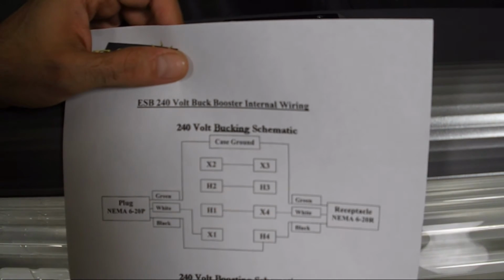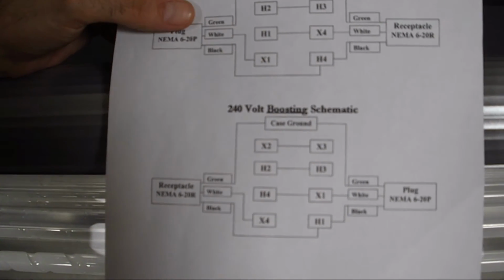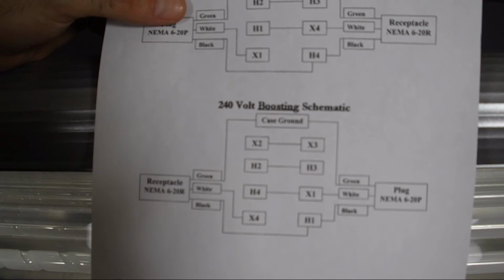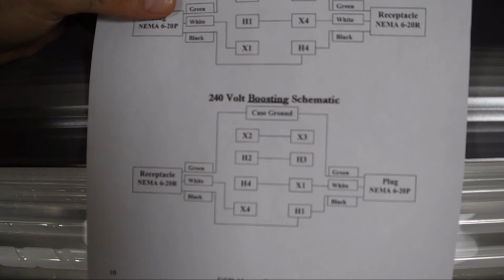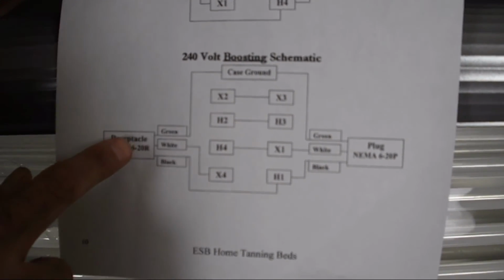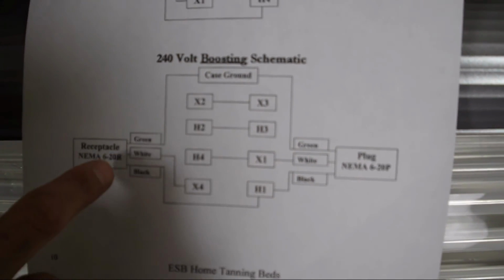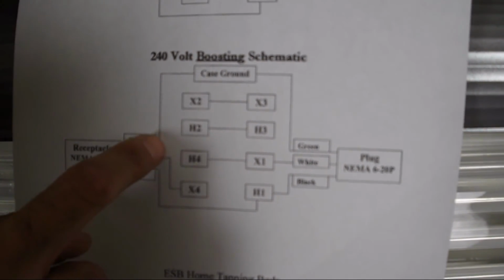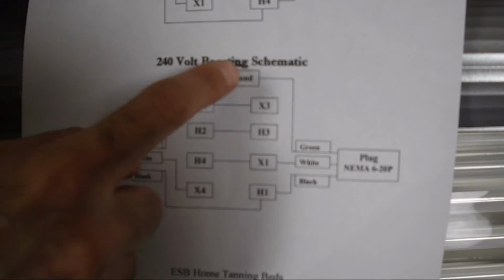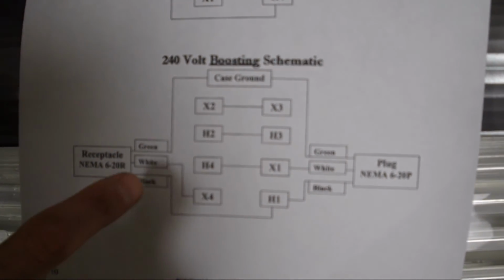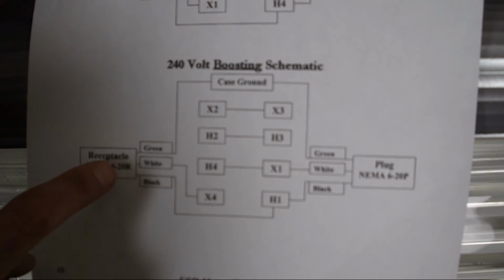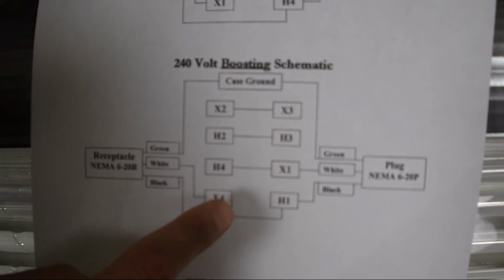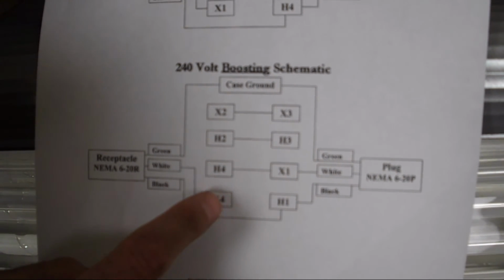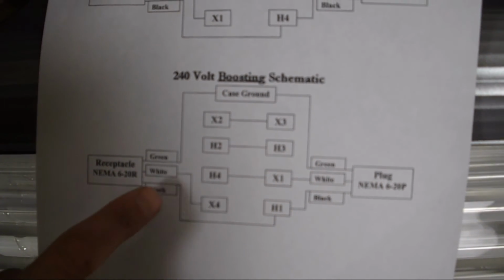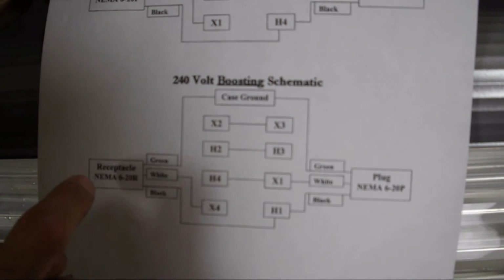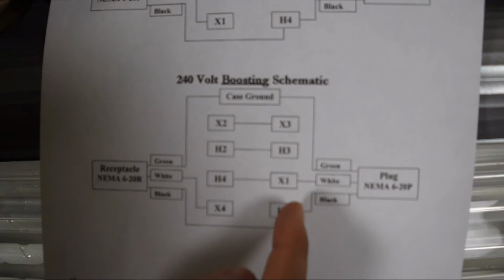as well first. Now, if you needed a boosting transformer, meaning that you would need to increase the voltage roughly 17 volts, you still have your receptacle and your plug, but they're going to be wired a little different. In this case, the green from the receptacle and plug still are both connected to your case ground. And your white from your receptacle is now plugged into X4 instead of X1.